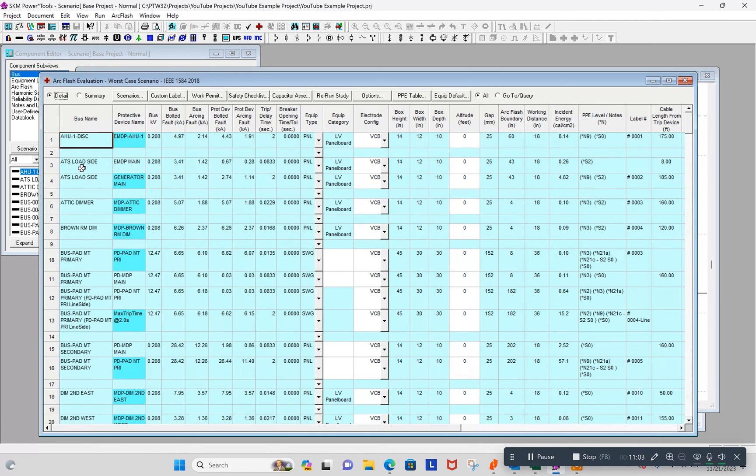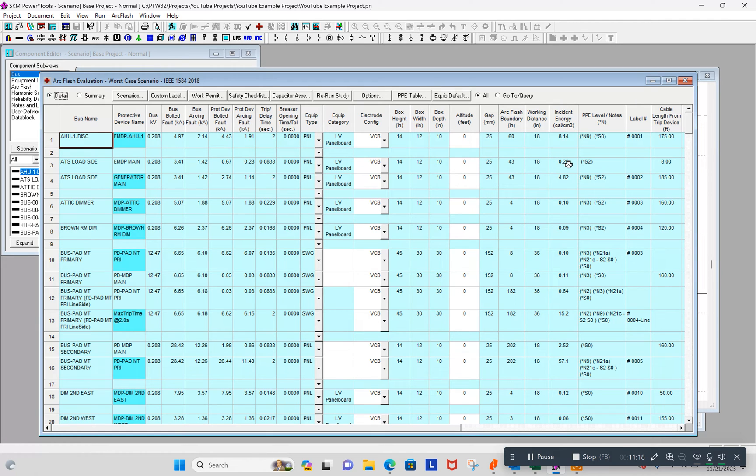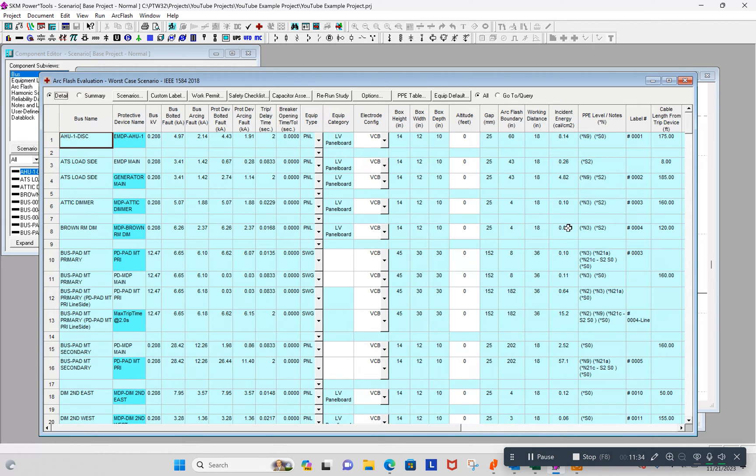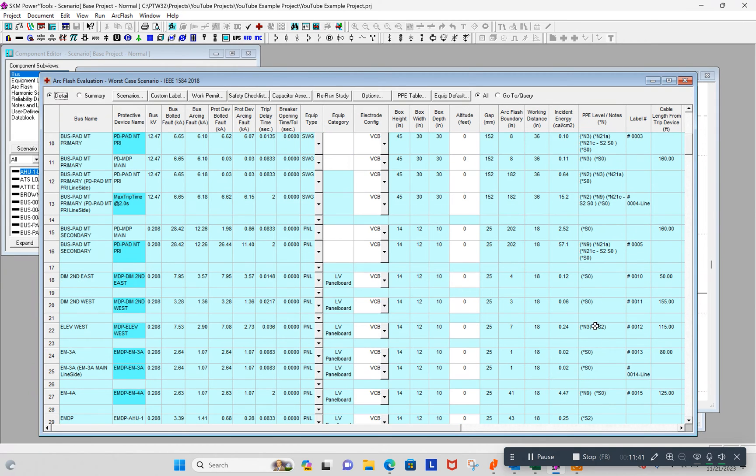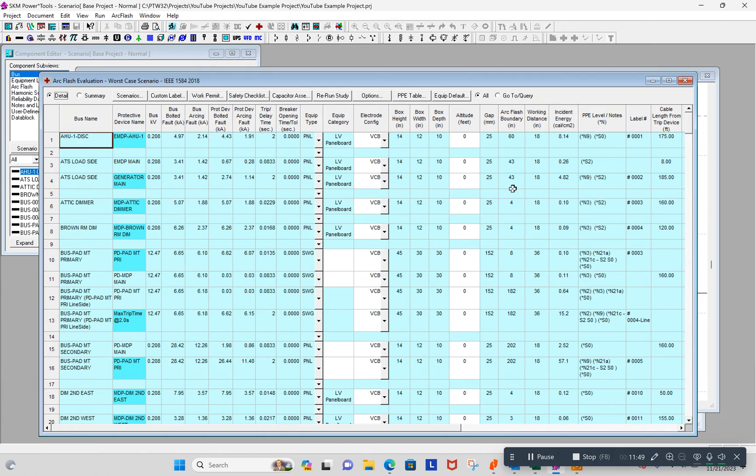So I can see that, yes, under my load on generator scenario, scenario 2, ATS load side, my incident energy, it's still very low, 0.26 calories. But that must be a little bit higher than it was under the base scenario only. And then the same with, oh, these are which device it's protecting it by, you're protected by. That's a different subject. So S0 would be the one base project and S2 or generator, load on generator where it turned out to be a higher incident energy. Let's see if we can remember those, the 0.26 and the 0.482.